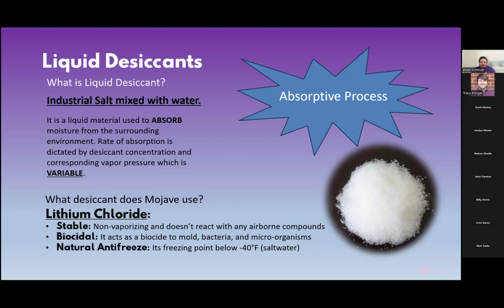It's also a natural antifreeze. For all those on the call, I don't think this affects any of us. I certainly know at negative 40 degrees Fahrenheit, I'm not going to be in the state of Florida anymore. But it does not start slushing until negative 40. So if there are projects that you're working on that are in extreme northern climates, again, this liquid desiccant does not start slushing until negative 40 degrees.